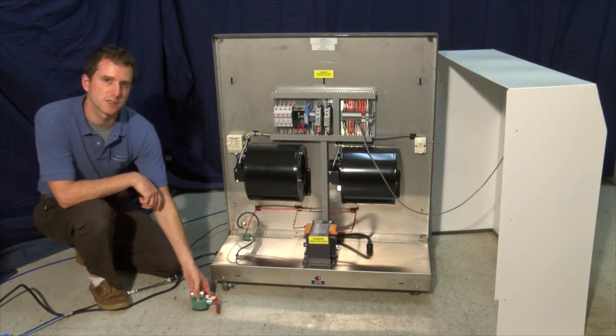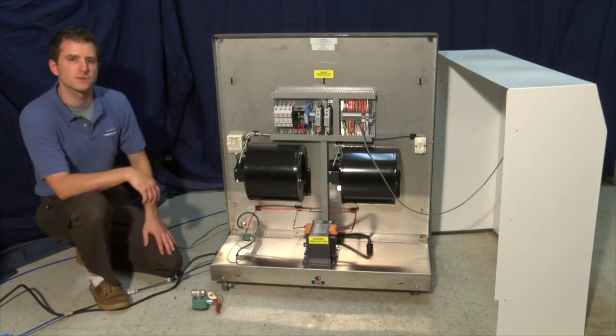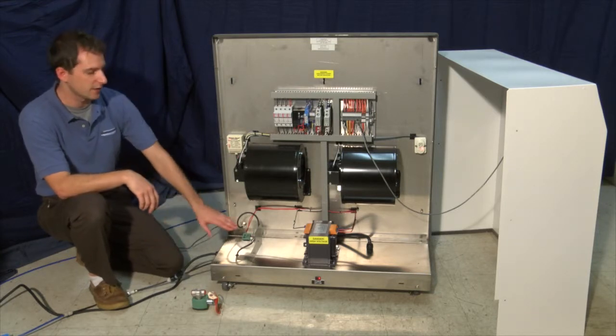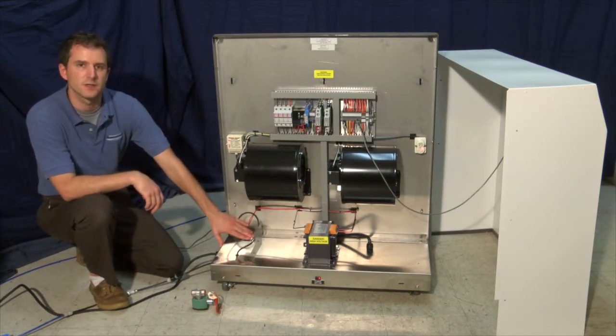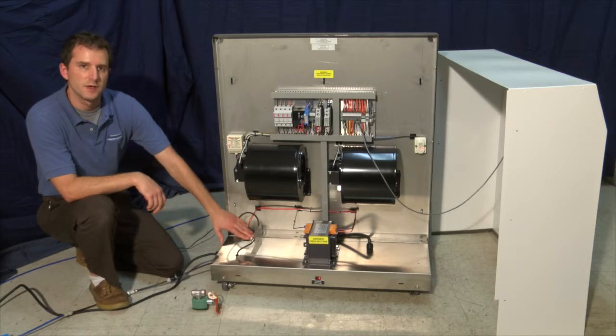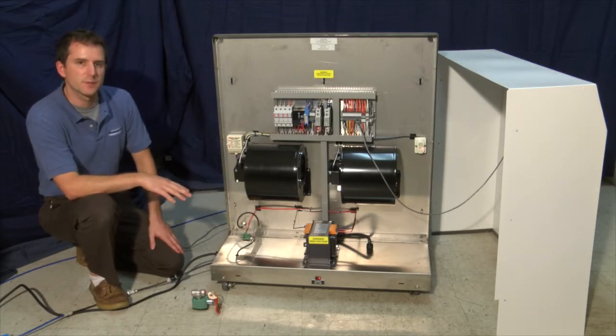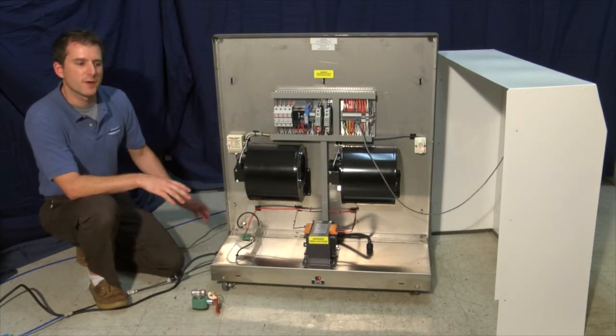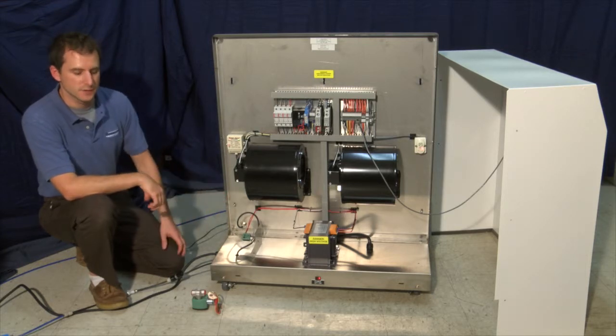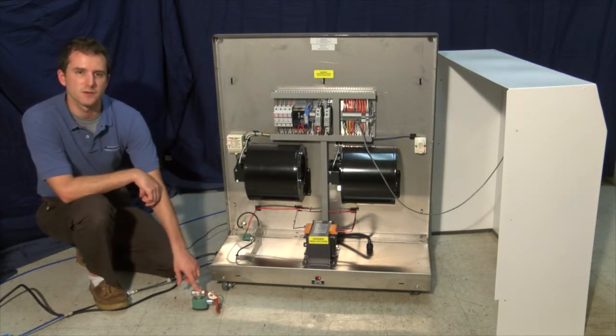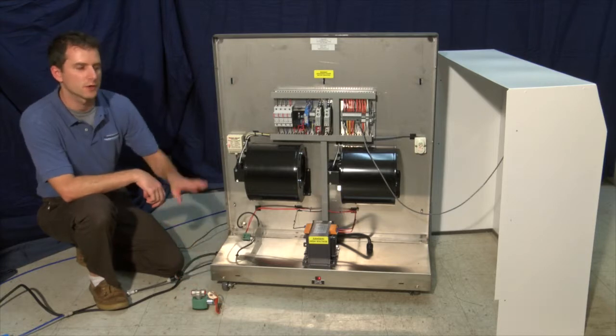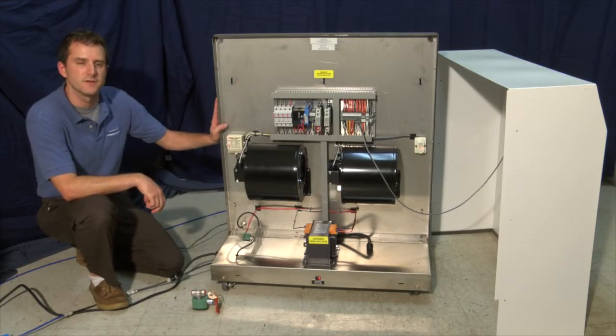This is important because the majority of overflows are caused by incoming debris in the water line sticking the fill solenoid and not allowing it to close. The mechanical nature of this problem is not resolved by electrically shutting down the unit. So the secondary flood guard solenoid ensures that there is no water supply to the humidifier in the event of a leak detection.